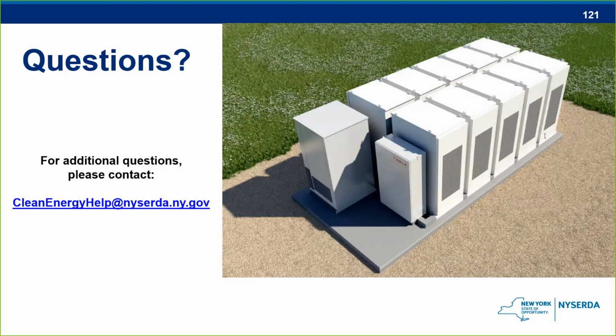Yeah, good question. So the large-scale testing, 9540A, is broken down into a couple of different phases. They start off with a cell phase, then they get into a module phase, and then they get into a rack phase. And then finally, the last phase is called the installation phase. And the installation phase dictates what type of fire protection is going to be used in order to control that fire. So if they're using a sprinkler system with a certain density, then that's the density that they tested it with, so that's the density that's needed for that particular system itself.